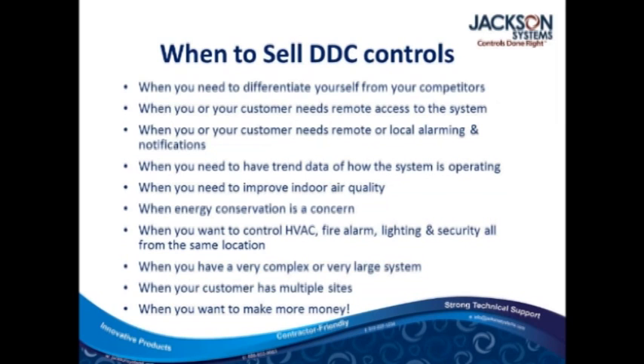Improving indoor air quality. A DDC control system can monitor CO2 in the building. It can monitor the amount of fresh air coming into a building. It can monitor IAQ, which is a reading that, kind of a little bit of the building material and glues and drywall and carpeting and all those things, all the stuff that gives off. You can monitor all of those things to prove the indoor air quality in a school or a building. Or maybe it's in a parking garage. We help out with a lot of parking garages these days.